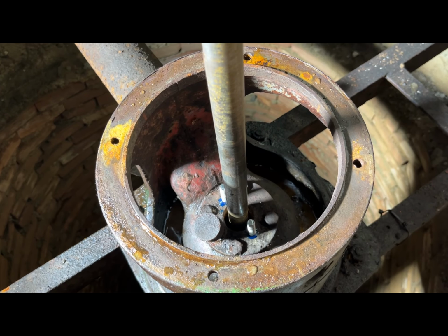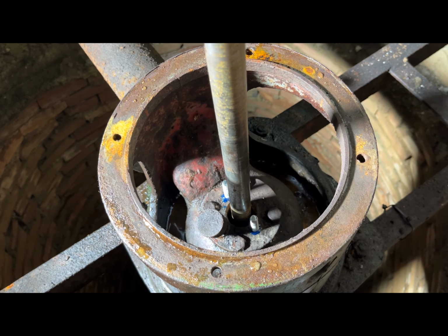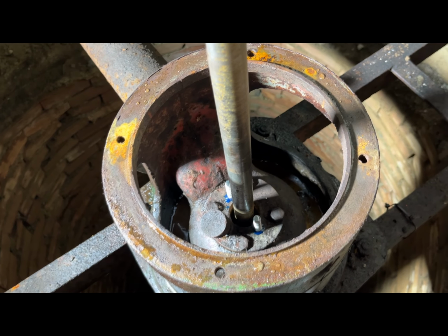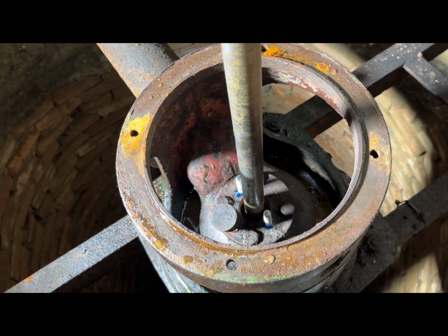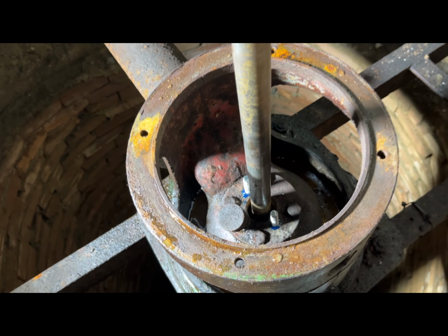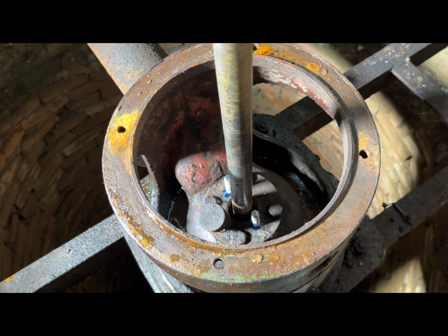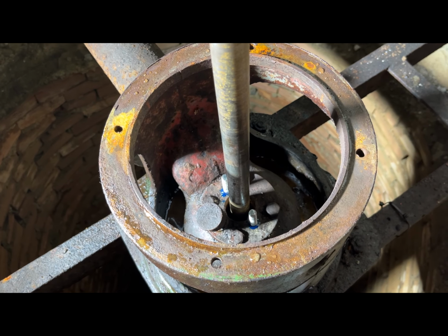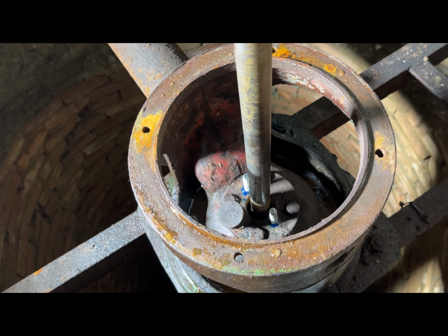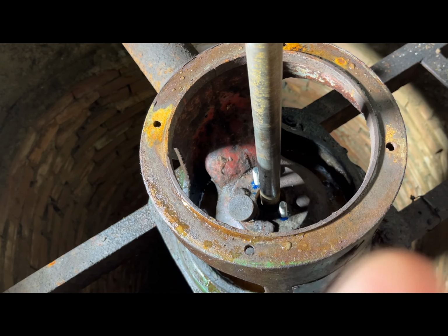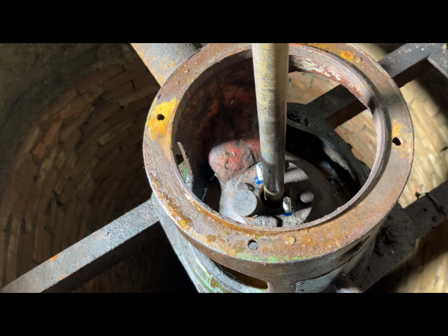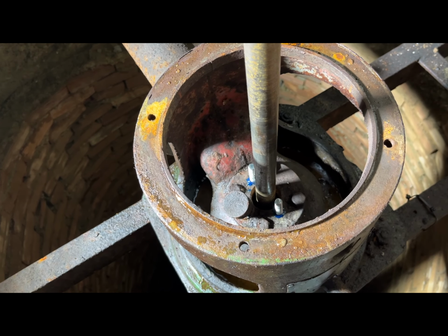Then you want to make sure that the studs aren't corroded, or better said, you want the nuts to move freely. You can try to clean them up, but in my case they were too far gone, so I actually replaced them. I used Loctite in order to keep the moisture out. You can also use anti-seize, but you risk removing the studs while trying to loosen the packing nuts.